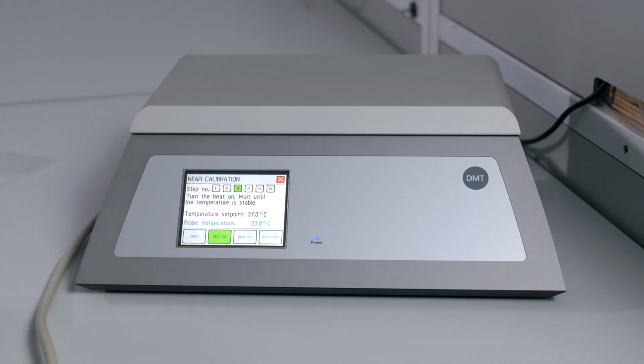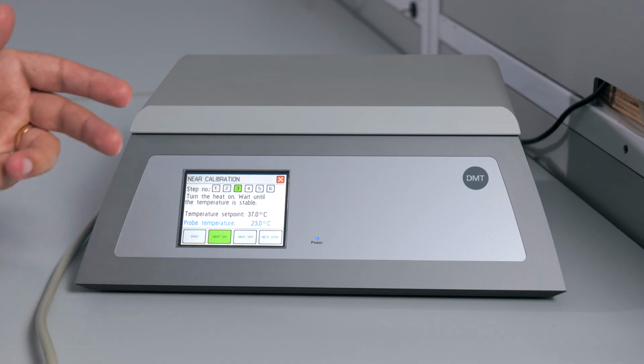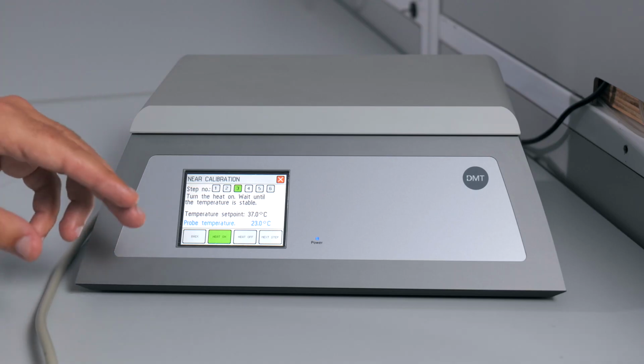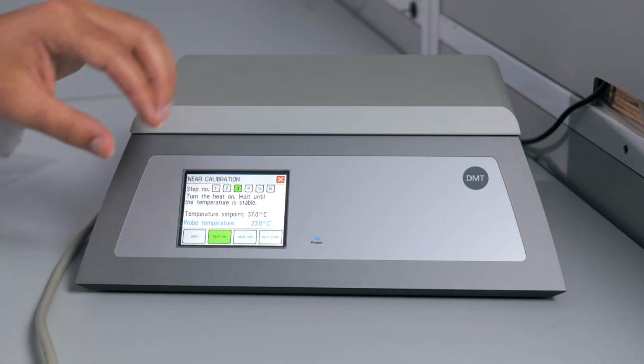Step 3 asks you to turn on heat for the calibration. As mentioned before, it's best done at experimental temperatures. However, it takes about 20 minutes for the chamber to warm up to 37 degrees Celsius. You do not want to do the calibration while it's heating, so you should either turn this on earlier, about 20 minutes before you start, or leave it off for the calibration.